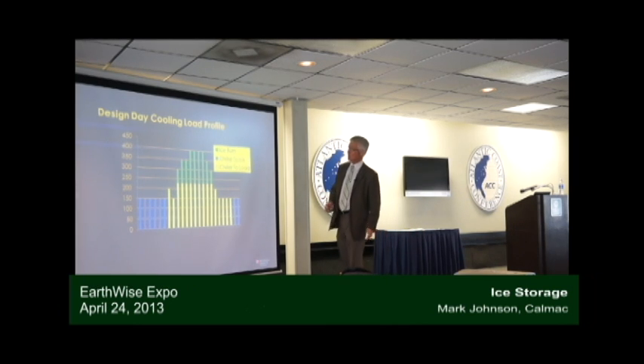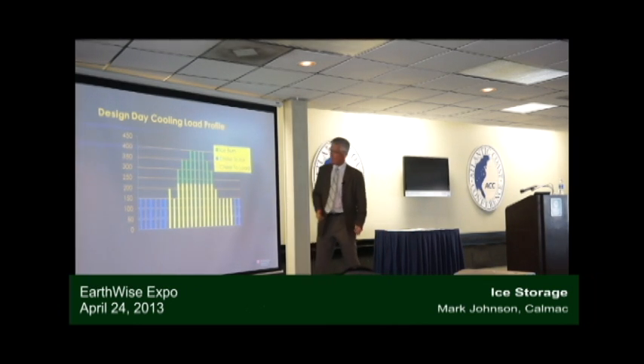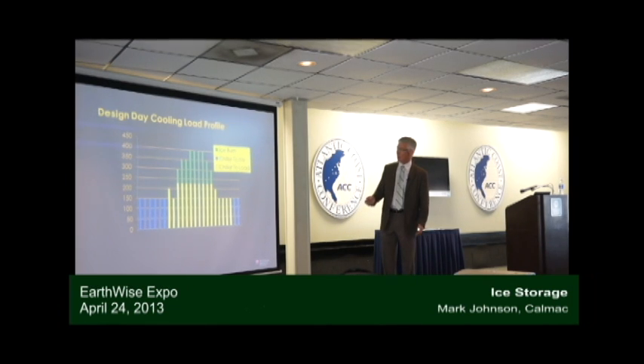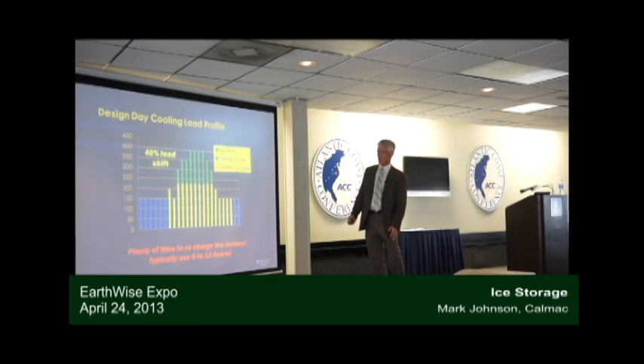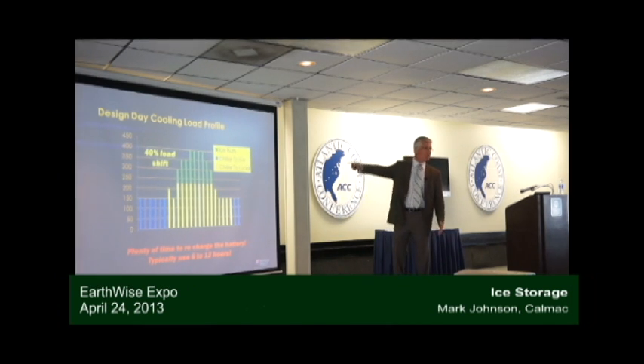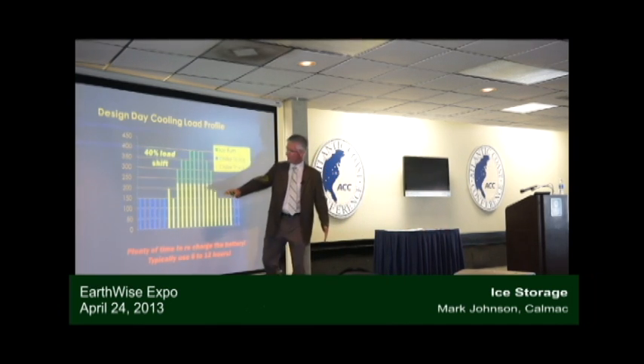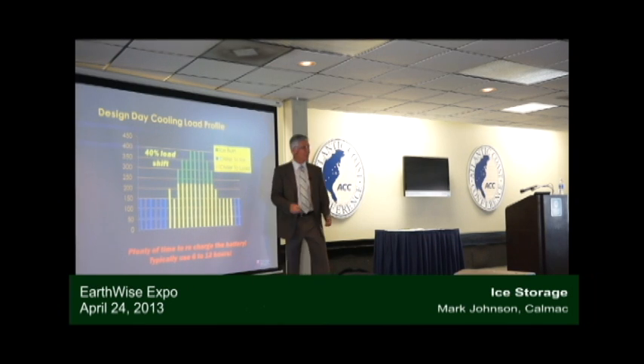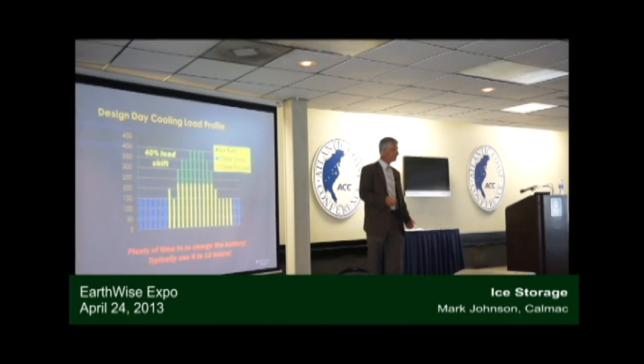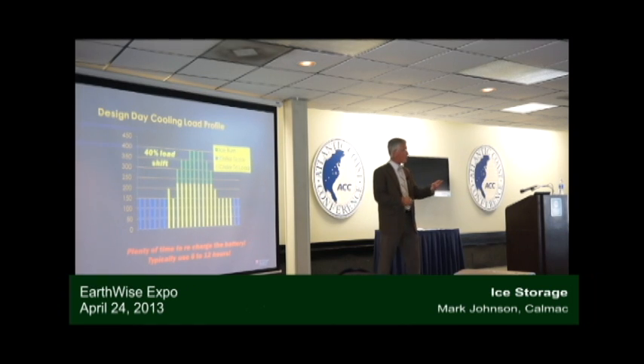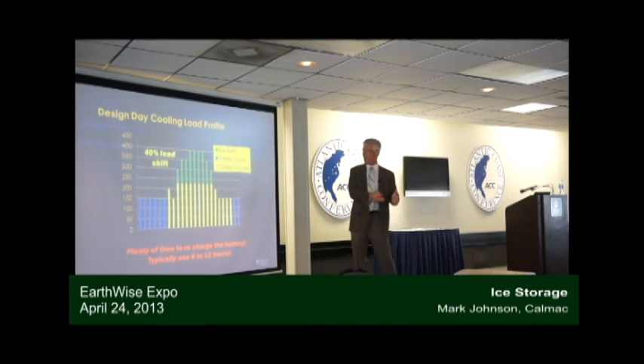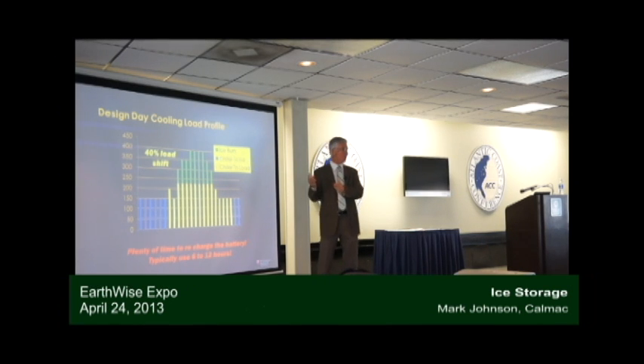So here's a case where we had about 8 hours at night to recharge the batteries, and we're able to shift about 180 tons of load, about 40%. So that's a good thermal storage application right there. If that load would have been flat for 24 hours, probably not a good thermal storage application. If it had been an elementary school or a church, spectacular thermal storage application. Why? Because on those kinds of buildings, that demand charge is an even higher percentage of your power bill.